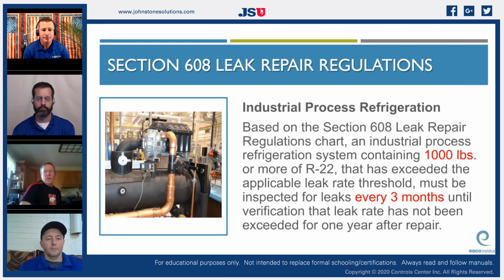Based on the section 608, here's the big stuff. Leak repair regulations chart: an industrial process refrigeration system containing 1,000 pounds of R22 that has exceeded the applicable leak threshold must be inspected every 3 months until verification that the leak threshold has not been exceeded for 1 year after repair. Kind of system you were just talking about, Clifton.